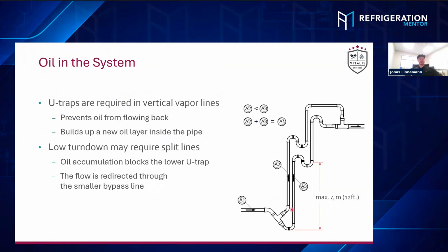And if you can't maintain the minimum needed velocity, even in a pipe with U-traps, then you would split those pipes up, right? So if you have whatever line size in the main line, you typically step down one line size for the main rising line, and the second bypass riser will typically be two sizes smaller. And the idea behind that is as soon as you drop below that minimum vertical velocity, you trap more and more oil inside that U. And at some point, you basically bypass the whole flow through that bypass rising line. And this bypass rising line has the smallest diameter. So you have still enough velocity to carry that oil back up to the compressor rack.